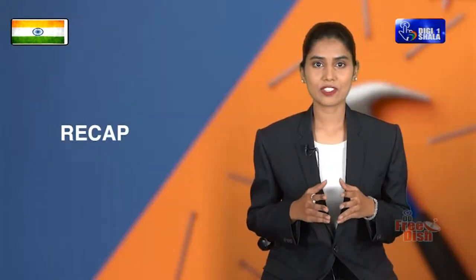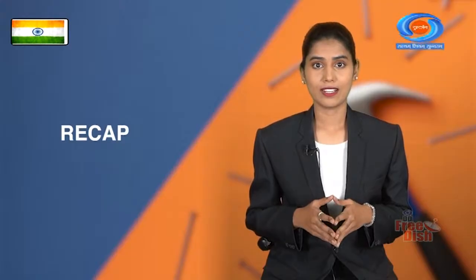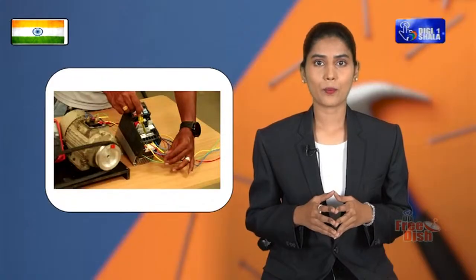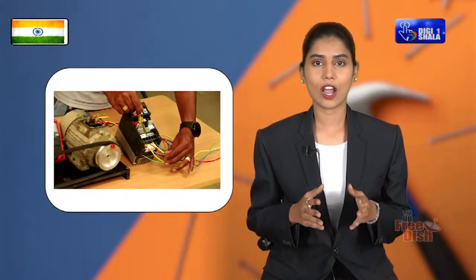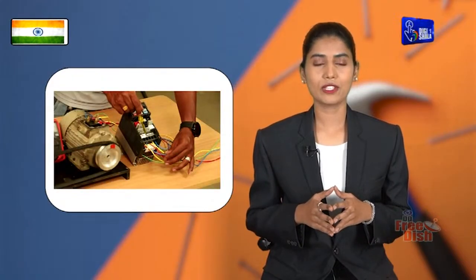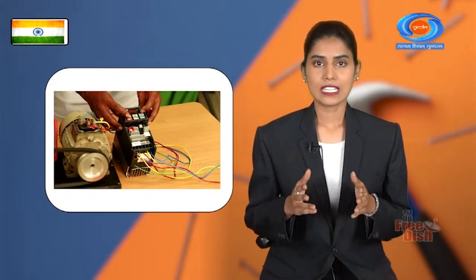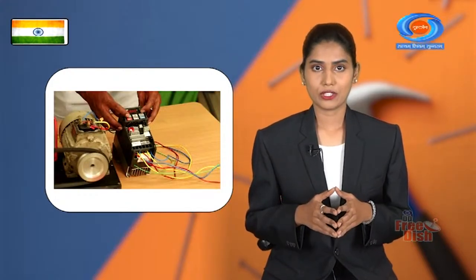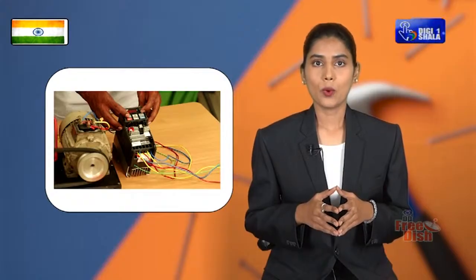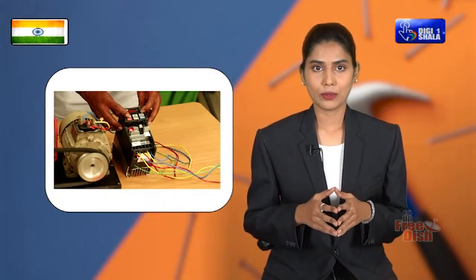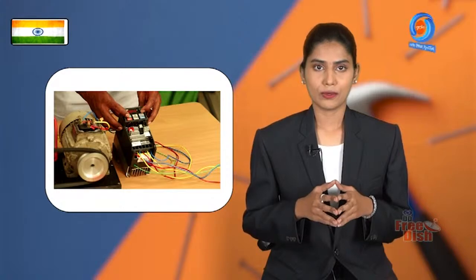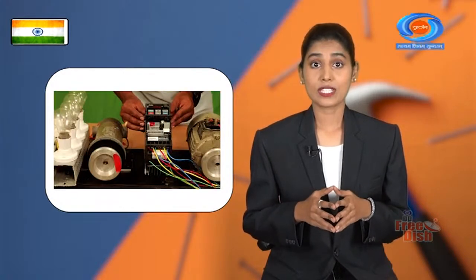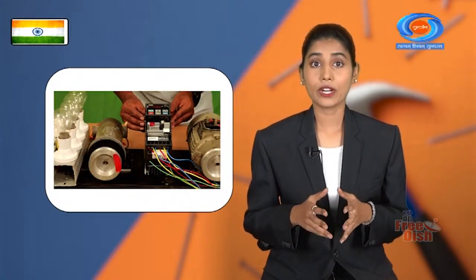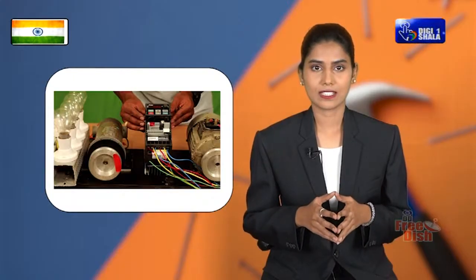Recap. Let us just recap what you have learned so far. Read and interpret details of the DC drive nameplates, and connect the input and output terminals of the DC drive to the motor to operate the load. Use the DC drive to control the speed of the motor and operate it with 1/4 load, half load, 3/4 load and full load. Use the DC drive to reverse the direction of rotation and operate the motor at different speeds.